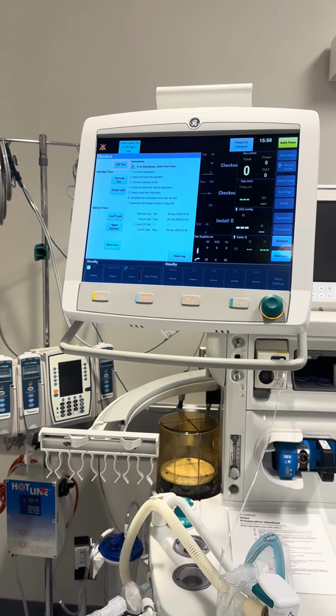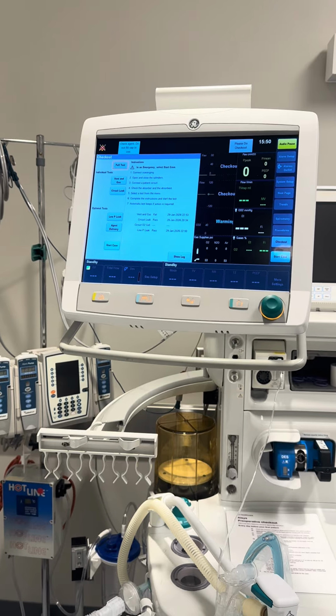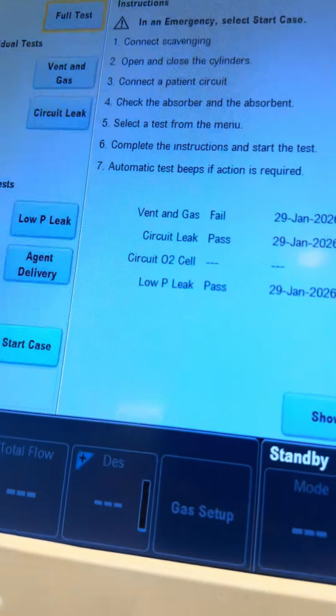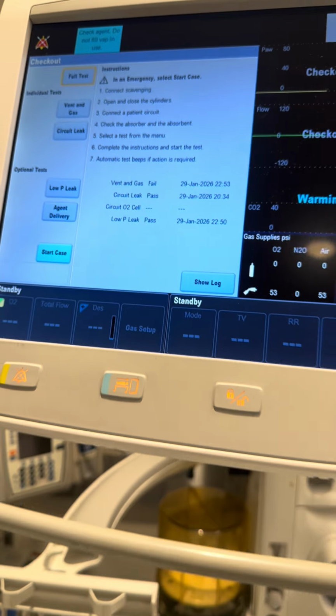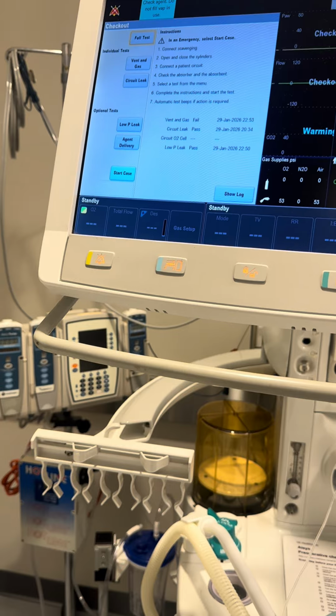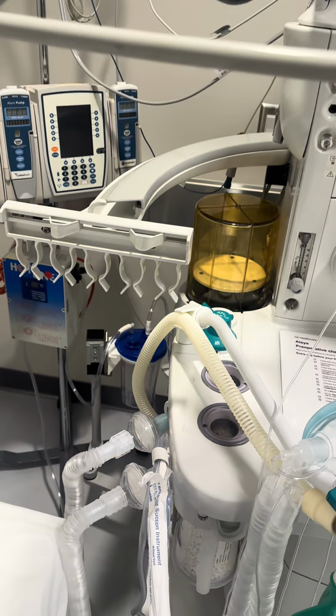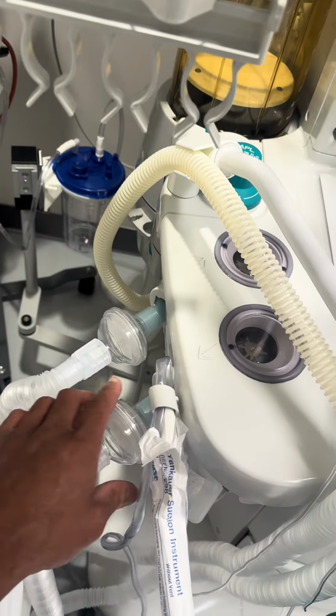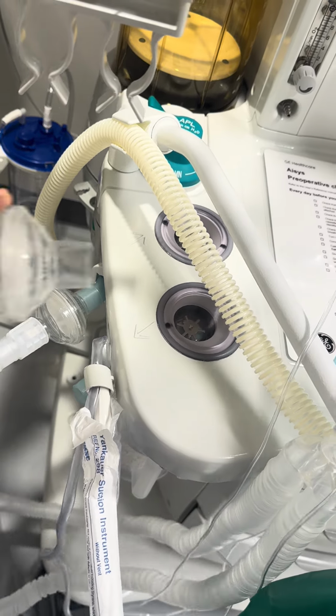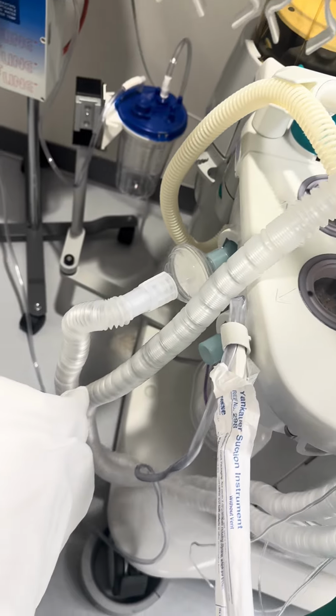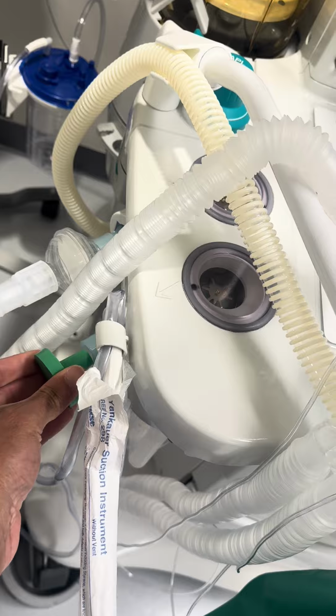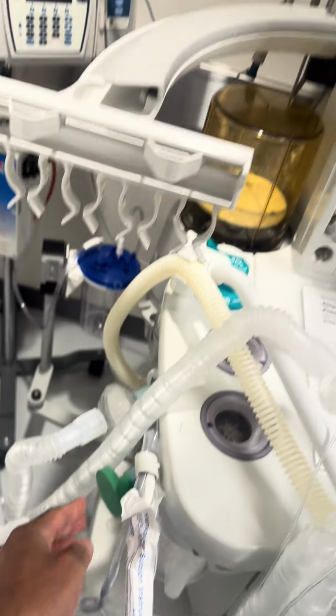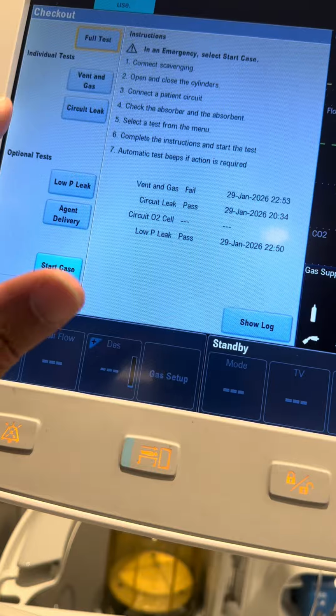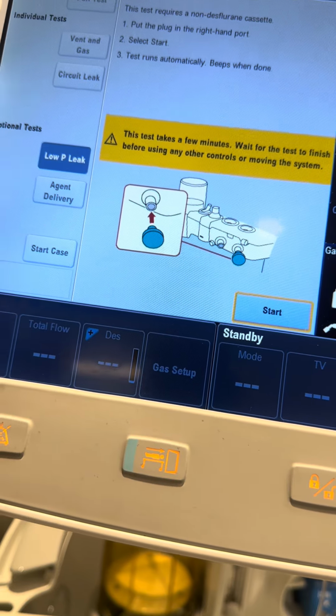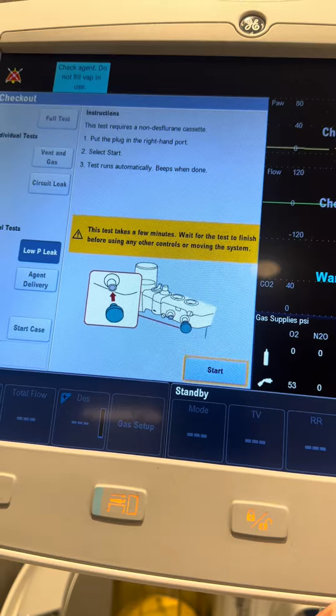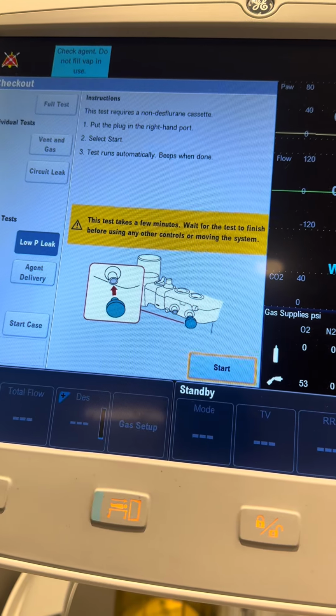All right, guys, so on the last part of our anesthesia machine check, we are going to do our low P leak. Now, this part is going to be a part of the anesthesia machine as well, but I want to do it in a separate video. So what we're going to do is you're going to take off the hose from the inspiratory side. We're gonna place our green plug inside, make sure it's firmly snug in there. And then you're gonna press low P leak. You're gonna follow the prompts, put the plug in the right-hand port, select start, and it's gonna automatically run.